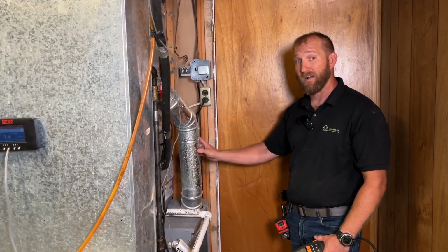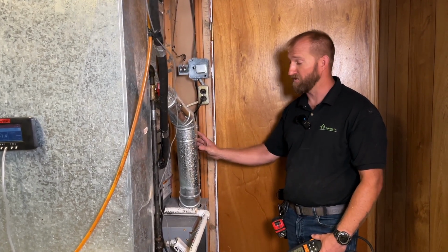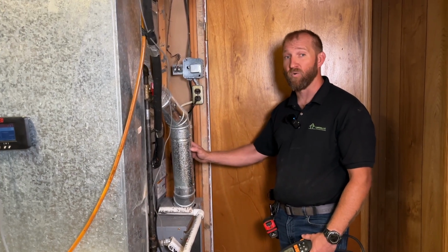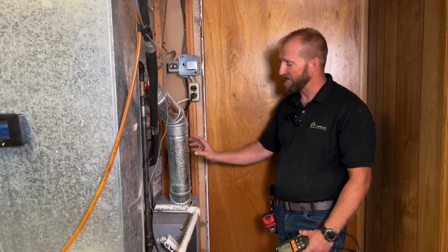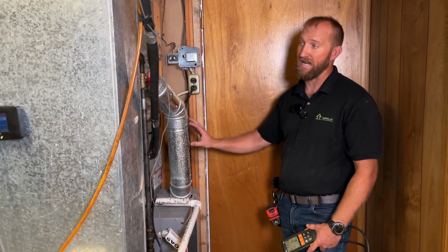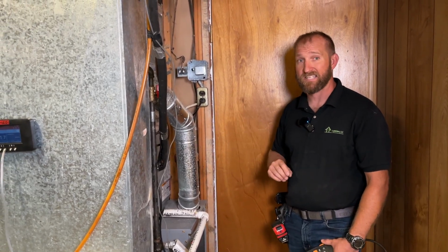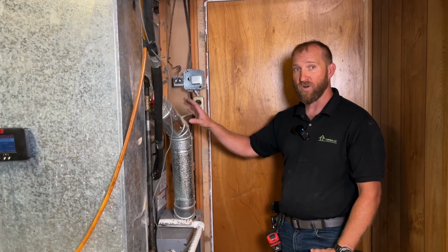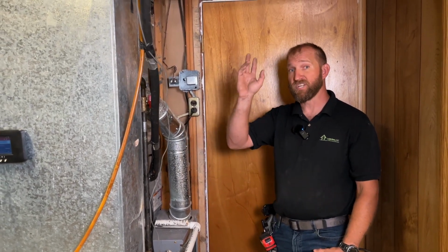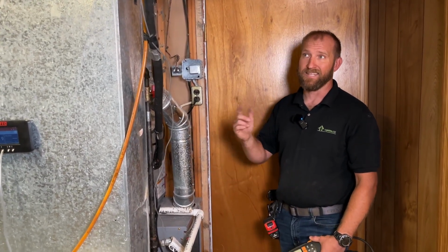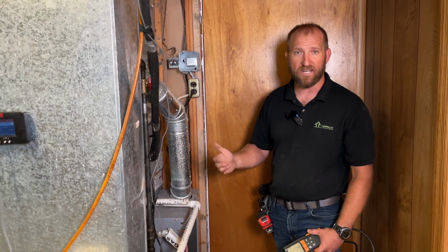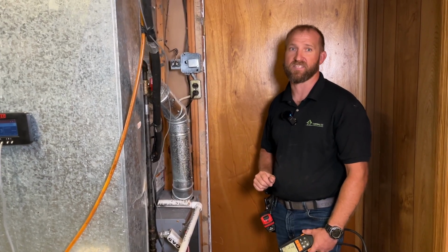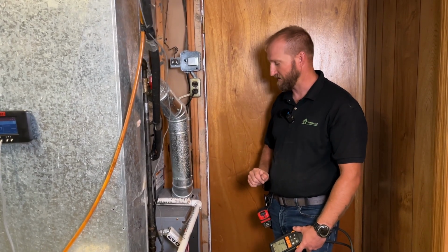Some companies and homeowners will allow you to drill into a single wall vent, not a double wall vent. Since this is all double wall vent right here, the BPI standard is actually for any sealed combustion or draft inducing furnace, you would test it at the exhaust point. In this case, it being on the roof, we're not going to get up on the roof because it might be unsafe to test at that point.